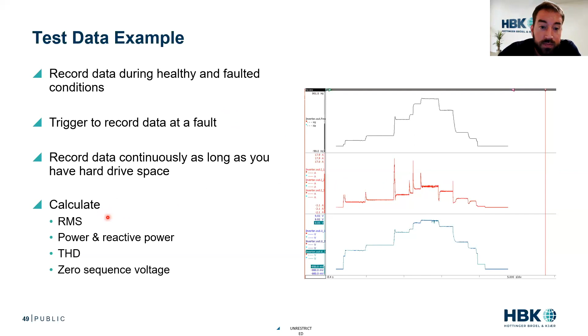So here's an example, showing plotted graphs of RMS voltage versus frequency and reactive power versus frequency. We can see that in my short circuit test, the values are all over the place. In my healthy test, we can follow them quite consistently. And in my demagnetization test, there's definitely an altered value.